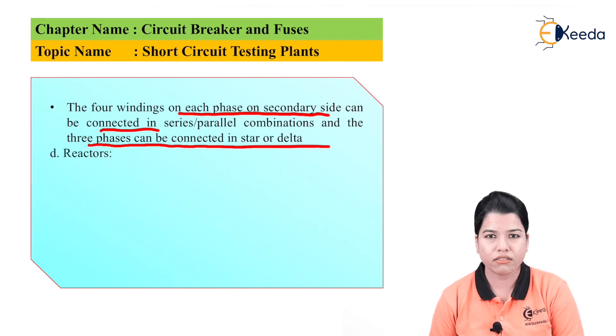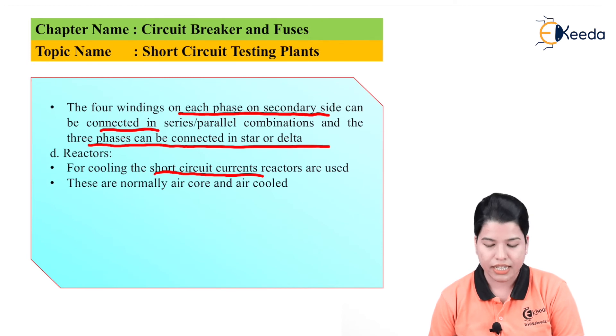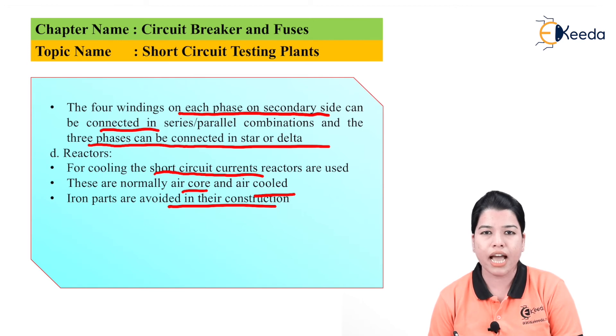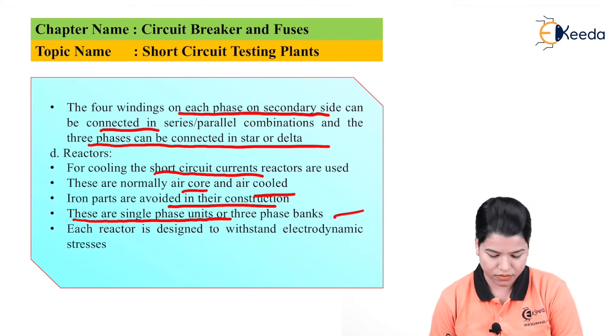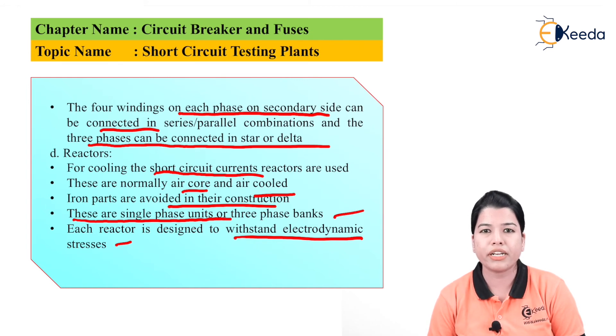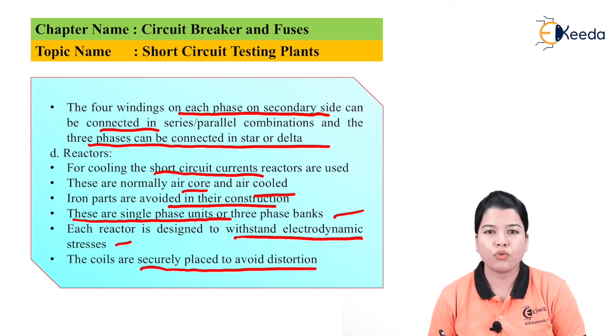Reactors are used for controlling the short circuit currents. They can be air-core or air-cooled type; iron parts are avoided in their construction. They are single-phase units or three-phase banks, and each reactor is designed to withstand electrodynamic stress. The coils are securely placed to avoid distortion.